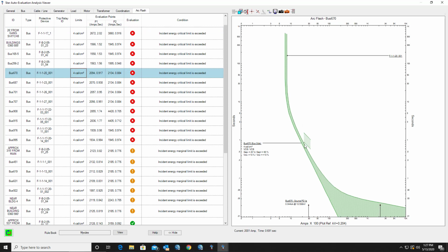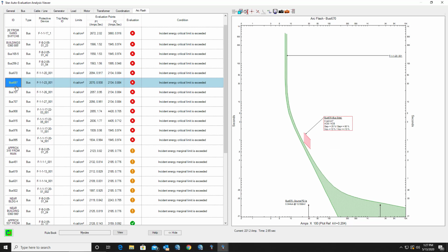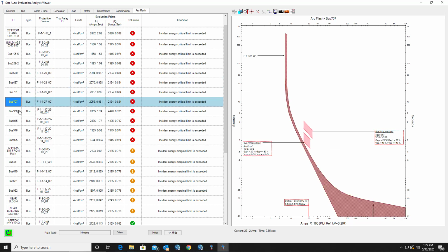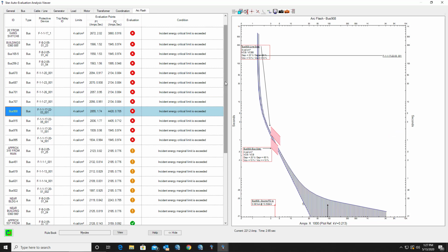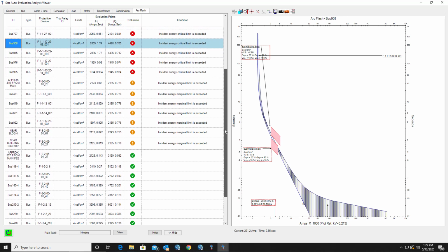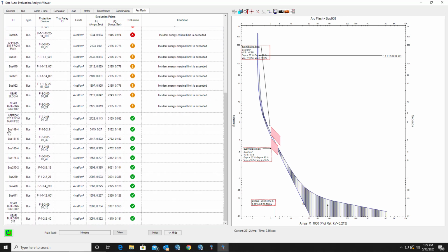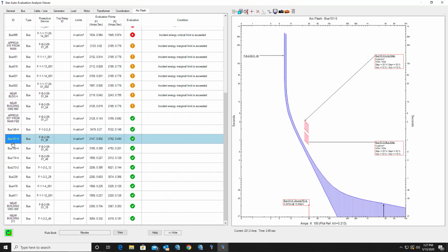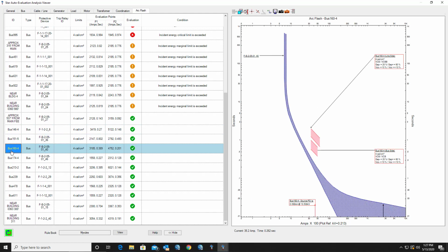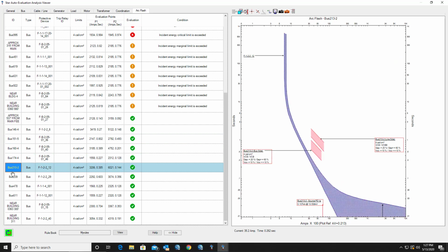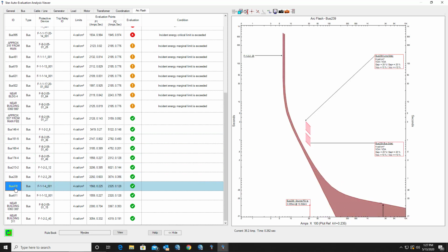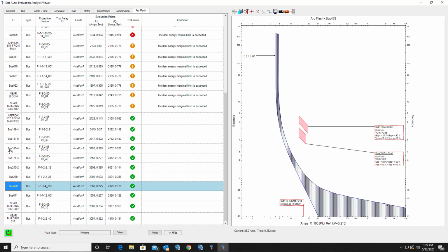They're close, as we can see here, but they still don't quite meet that energy value. So we can see several examples where the 4-calorie limit that we have respected globally is not met. However, we do have a lot of locations where the 4 calories that we had as reference is passing. So we can see automatically several of our locations are acceptable and are within the 4-calorie limit that we might have predetermined was acceptable for these locations.